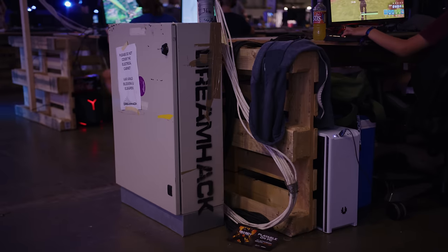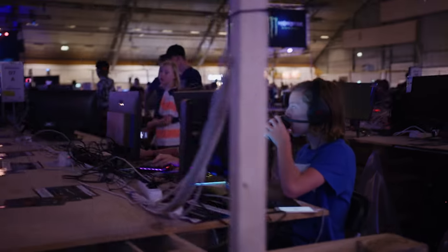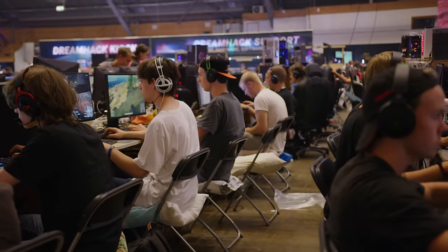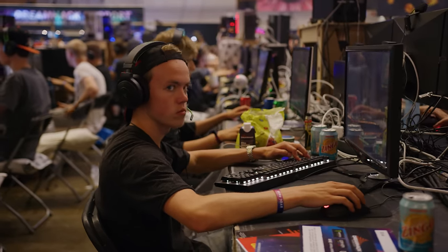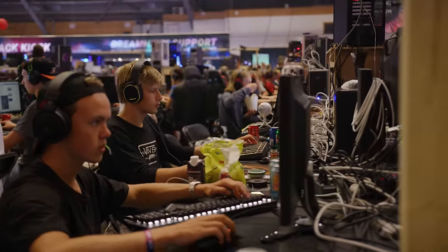These power distribution boxes were actually custom-made for DreamHack. The older ones can handle two rows of LAN attendees, while the new ones — largely due to computers and monitors getting more energy efficient — can handle three rows. They're also secured with RCD so that if leaking current is detected, like someone putting a finger in a socket or spilling a drink on a power bar, the power is immediately cut to the group and a maximum of only eight computers go down.